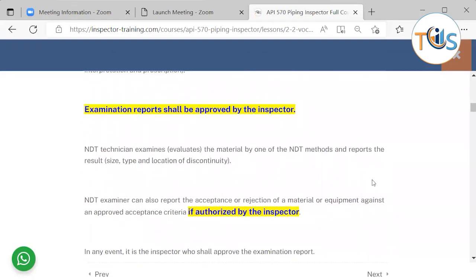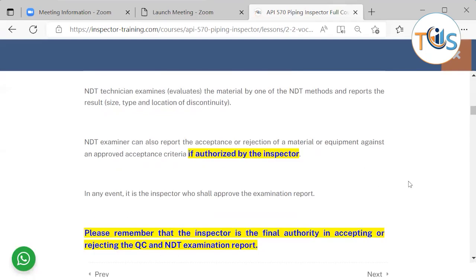The inspector does not need to be a qualified NDT examiner. The NDT technician examines or evaluates the material using one of the NDT methods or techniques and reports the results — including the size, type, or location of a discontinuity. An NDT examiner can also report the acceptance or rejection of a material or equipment against an approved acceptance criteria if authorized by the inspector, so they can do the interpretation as well. In any event, it is the inspector who shall approve the examination report.